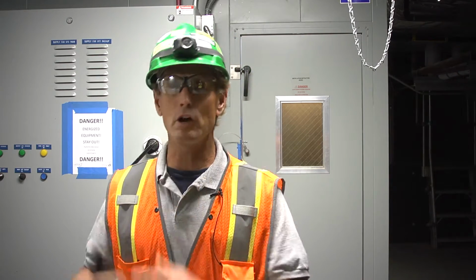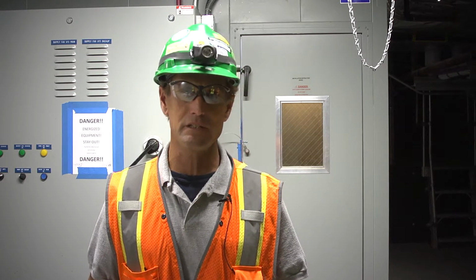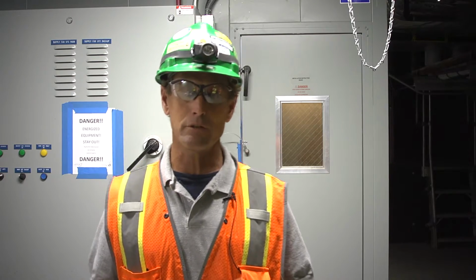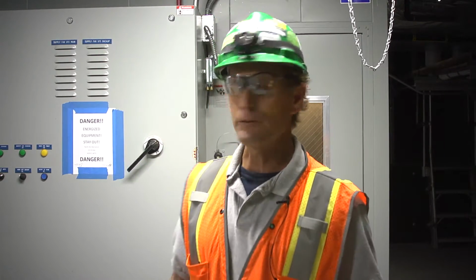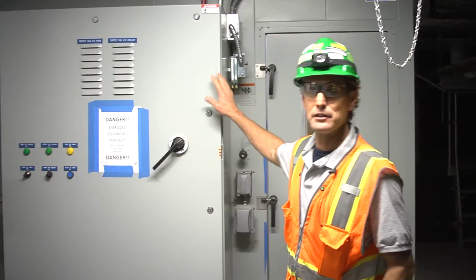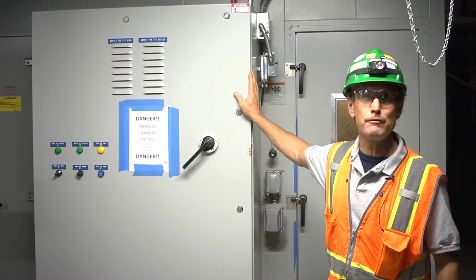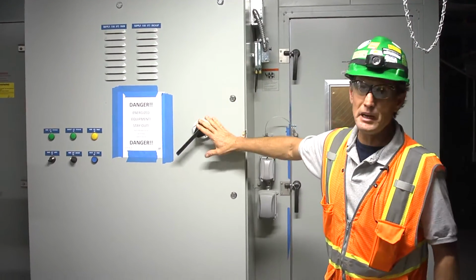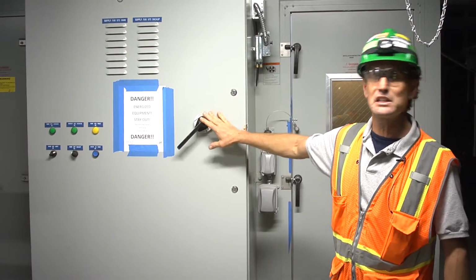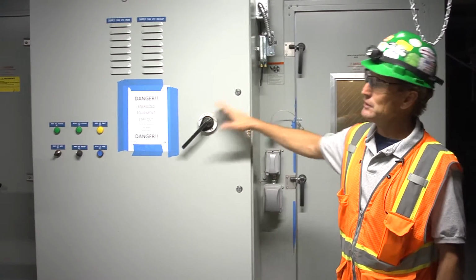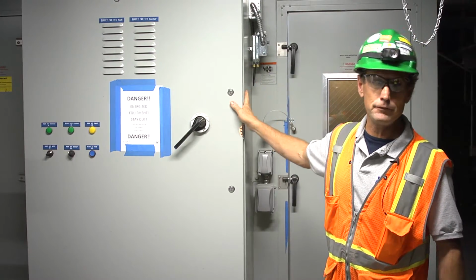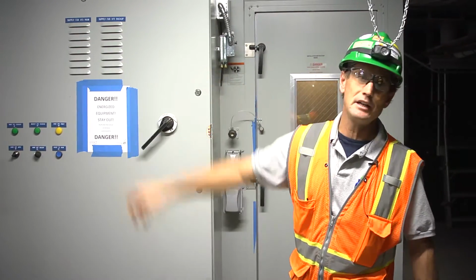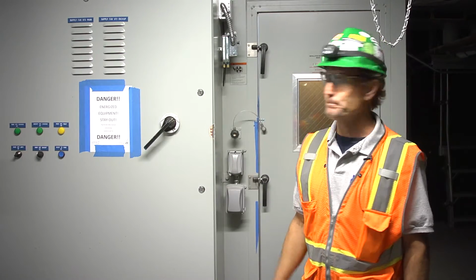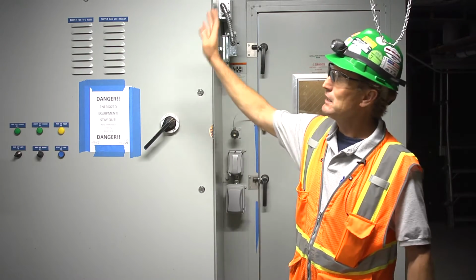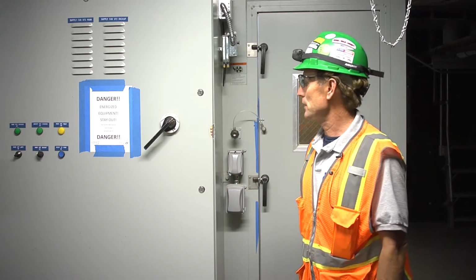So we're going to go through this air handler and identify the maintenance and safety and operational procedures of the air handler. First off, this is the single source power panel for the unit, and this is the main disconnect for the unit. When this disconnect is cycled off, it shuts off power to both the return fan, the low voltage circuitry, and the supply fan. Actually, this is the supply fan side, and the return fan is at the other end of the unit.